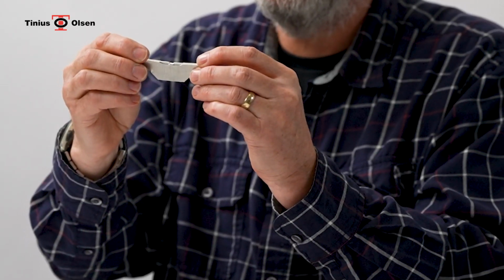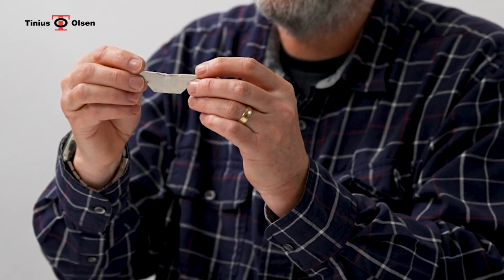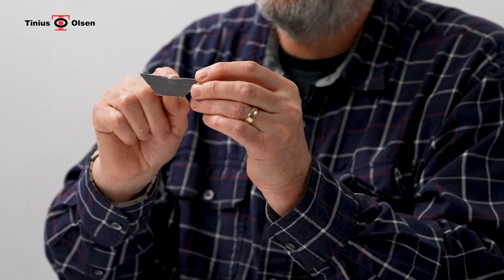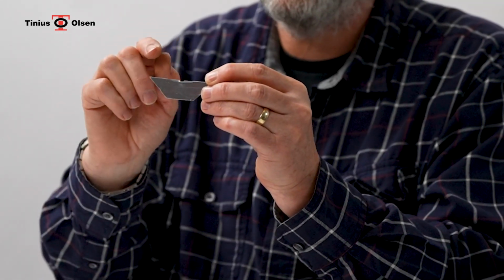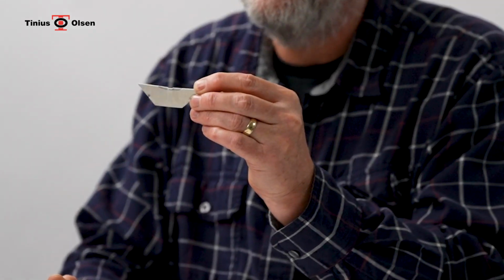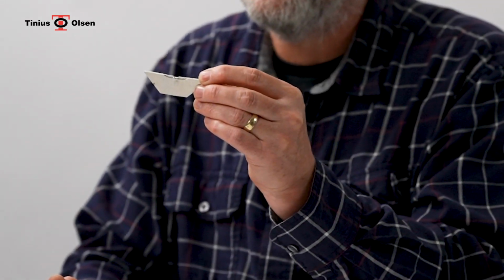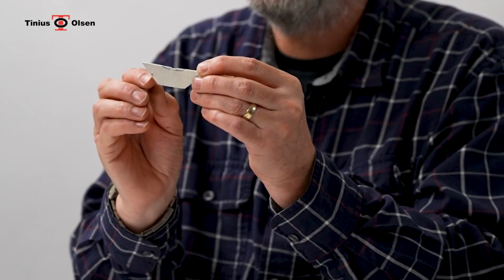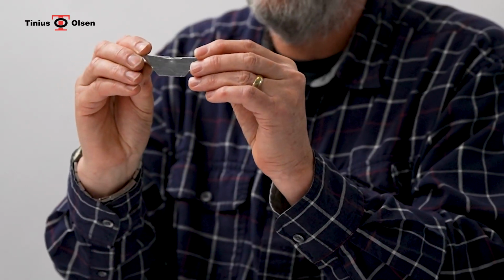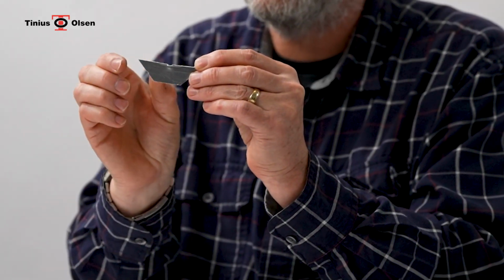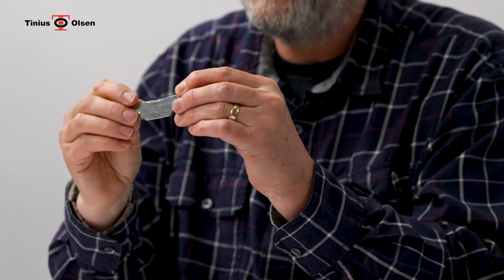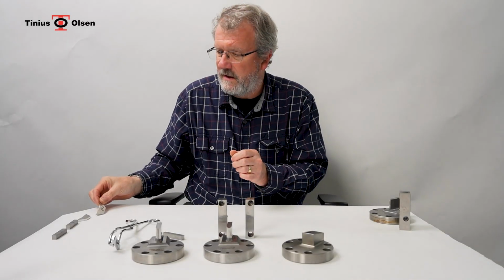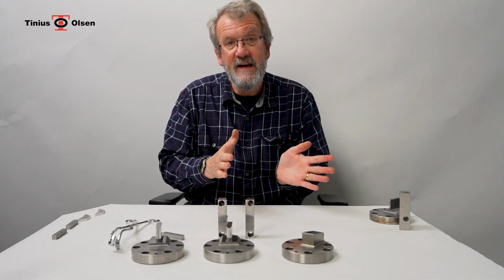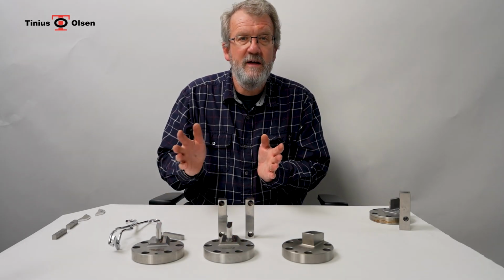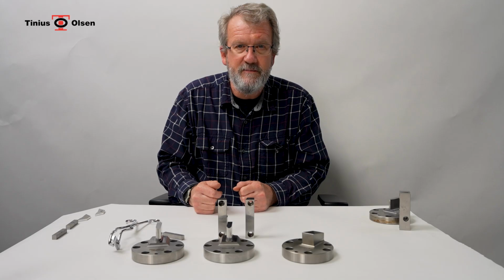This is then measured on our comparator here in the office, and we compare the radii that we see from this impression against what the radii are required to be according to the ASTM or ISO specification, and we can monitor the radii of the anvils at the same time, along with spacing and centering. This is direct calibration. The indirect calibration is where NIST specimens are tested.